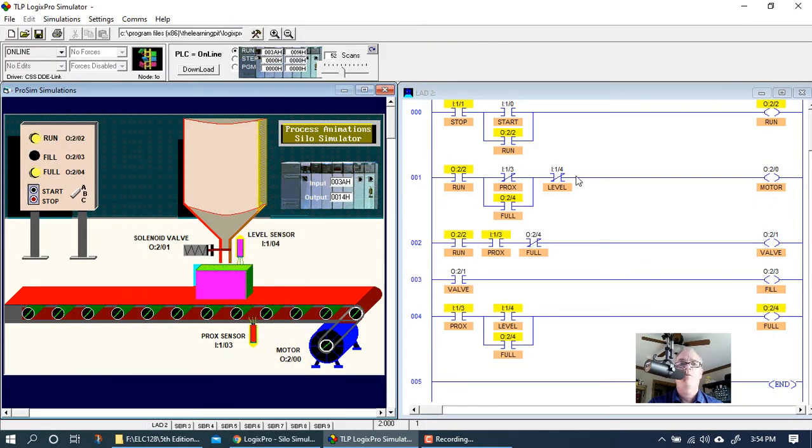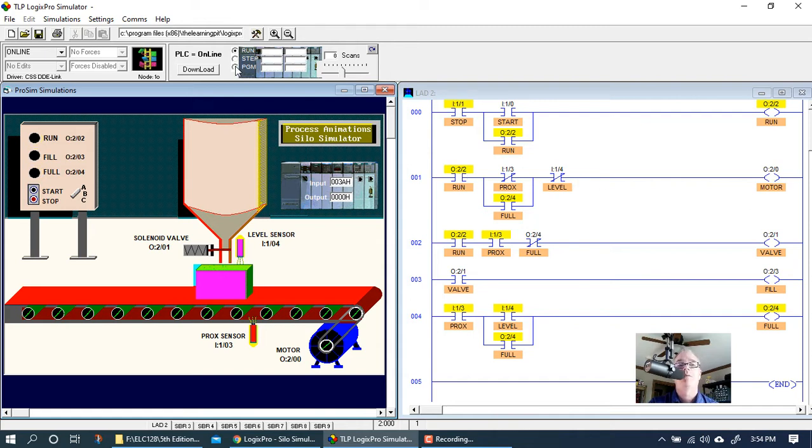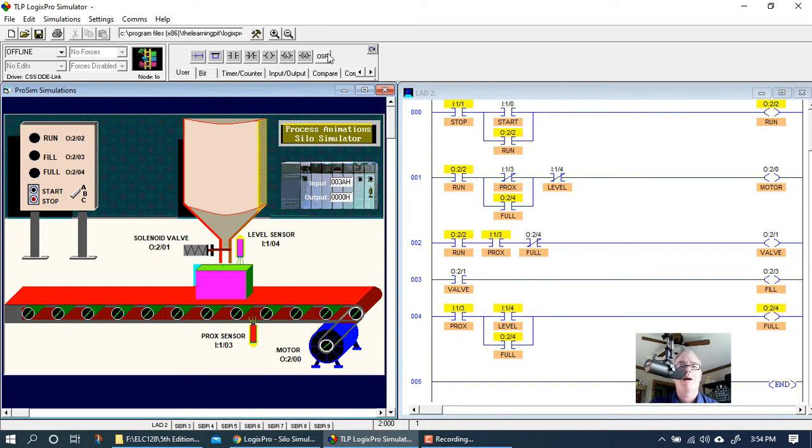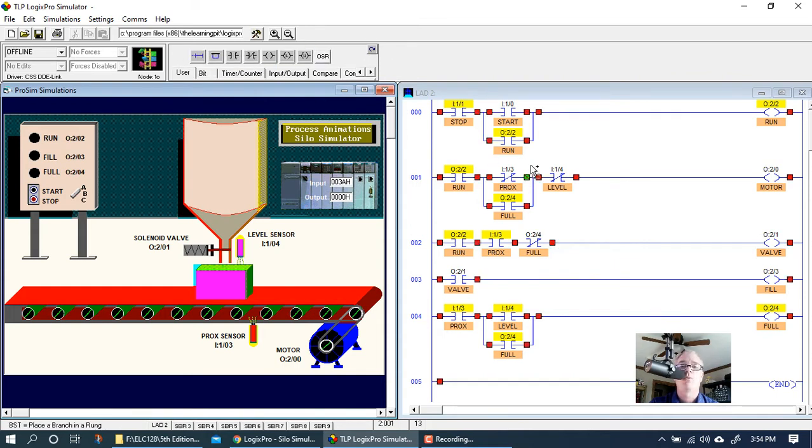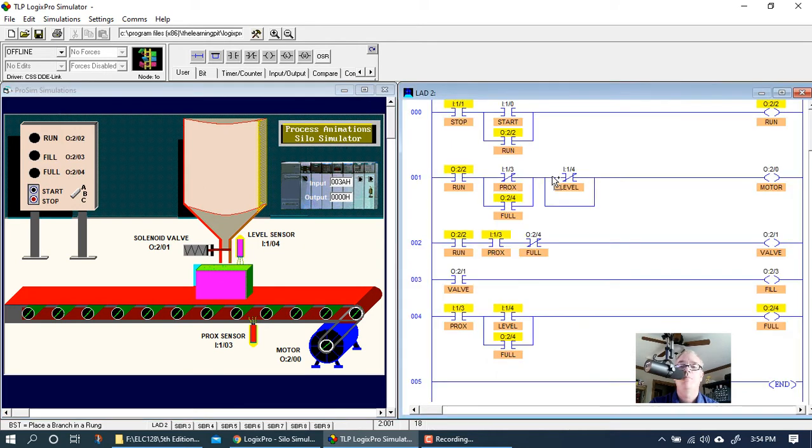So the first thing that comes to mind is, all right, if we want this motor to start back up with the start switch or the start button, what's keeping it from starting back up right now is this level switch that we put in—the instruction for the level sensor. So I've obviously got to put a bypass in around that.